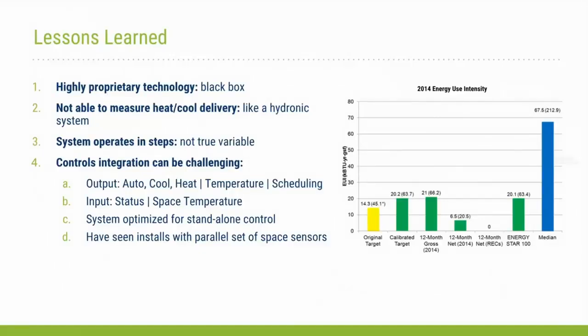And so one of the things that we were challenged with during the M&V period of this project is to say, do the results actually match the model results? And if there is a deviation, is it because of the way the system is installed, or is it because of operating conditions, or is it because of some limitation in modeling software? So it's one thing that we had to consider in the post-occupancy stage. Although variable is in the title of variable refrigerant flow as a system, the operation is not a continuously variable modulation, but rather is actually in steps.